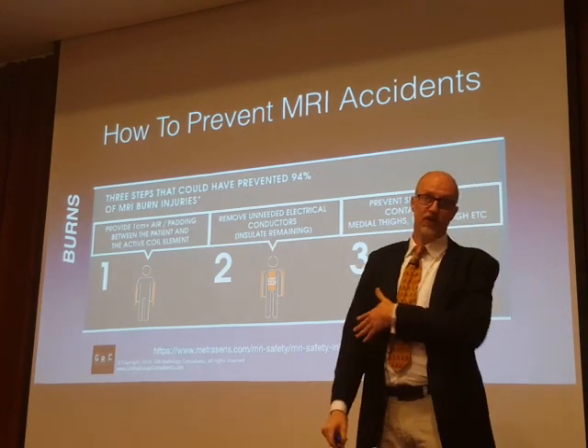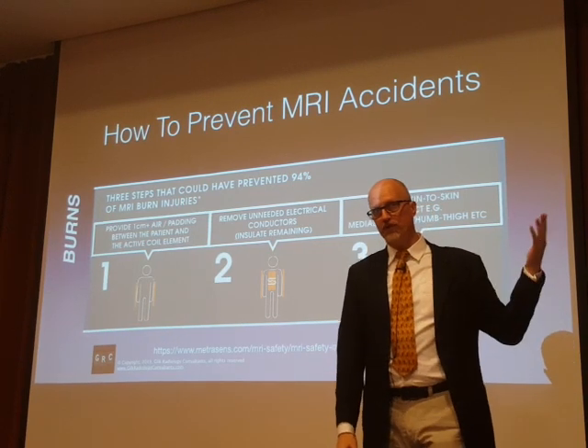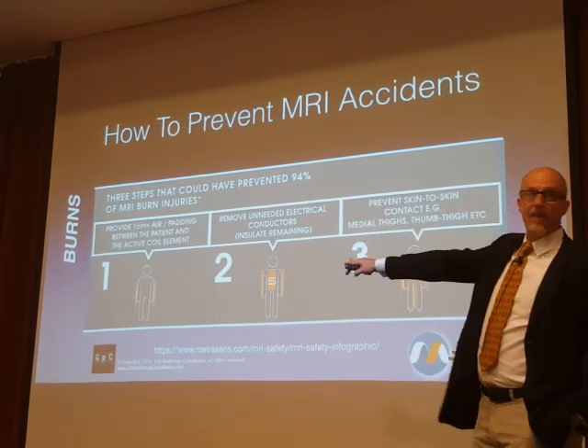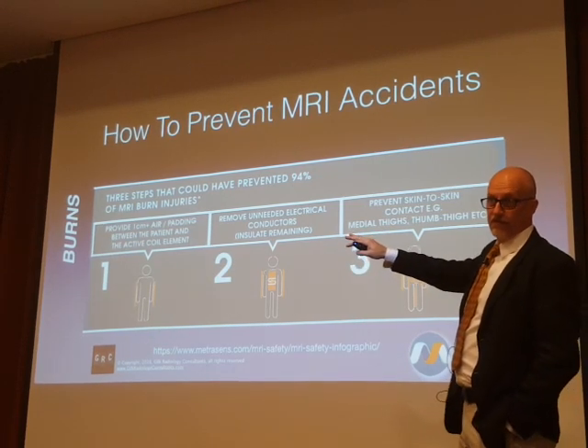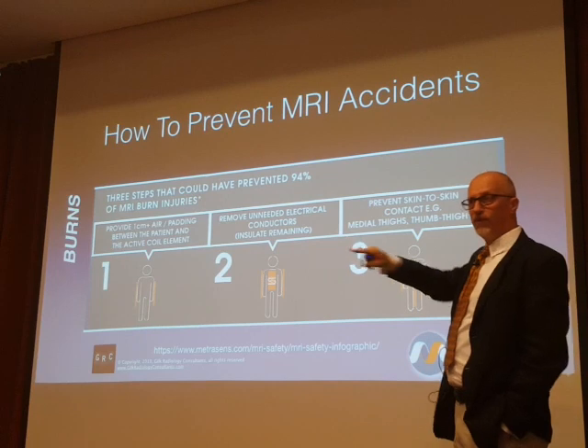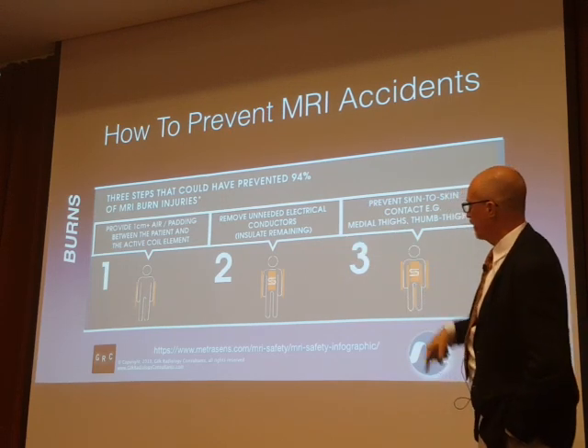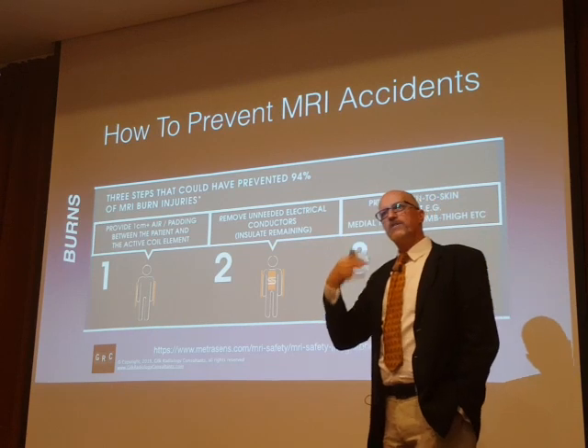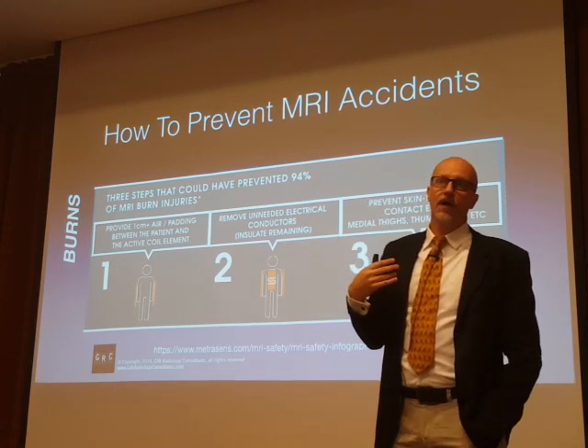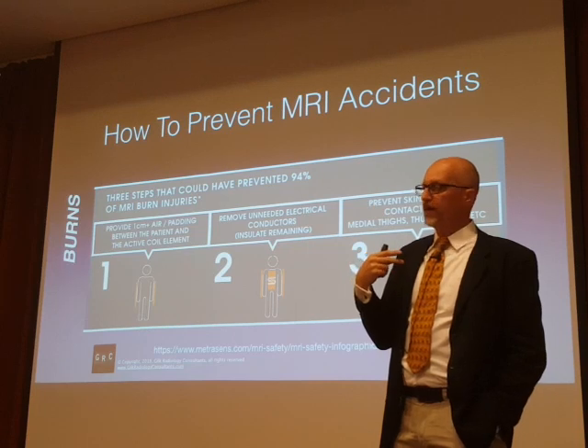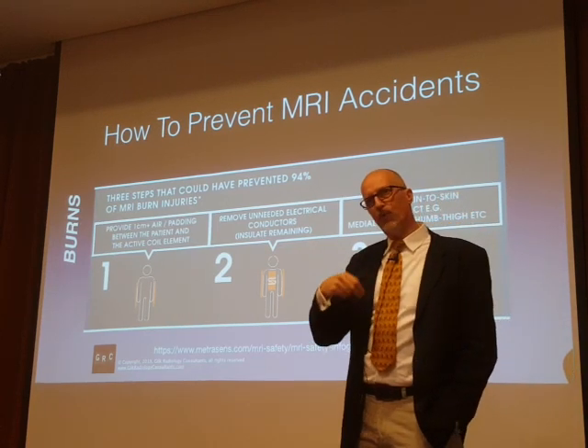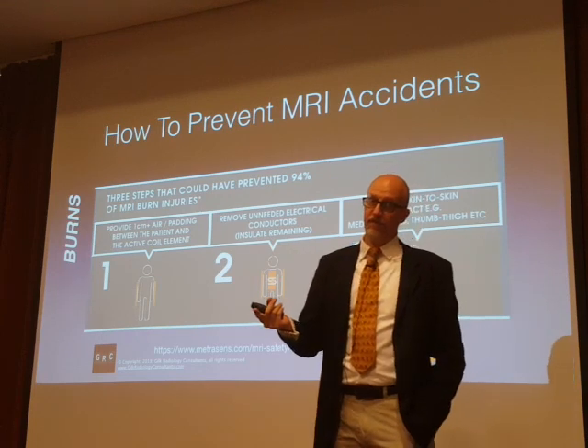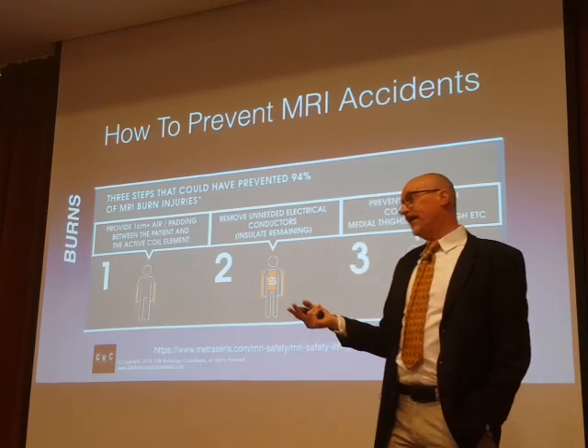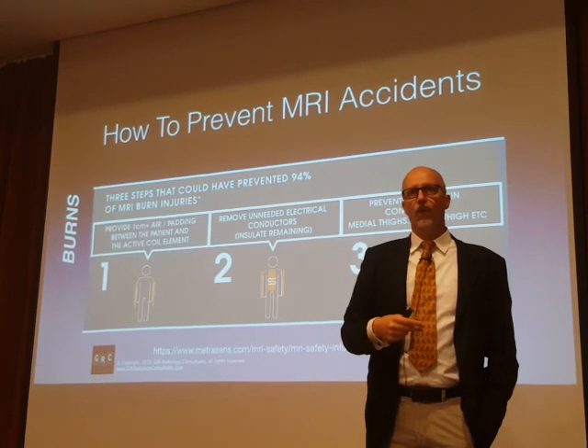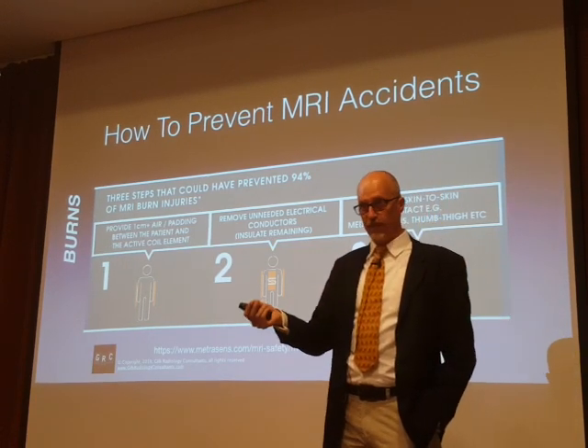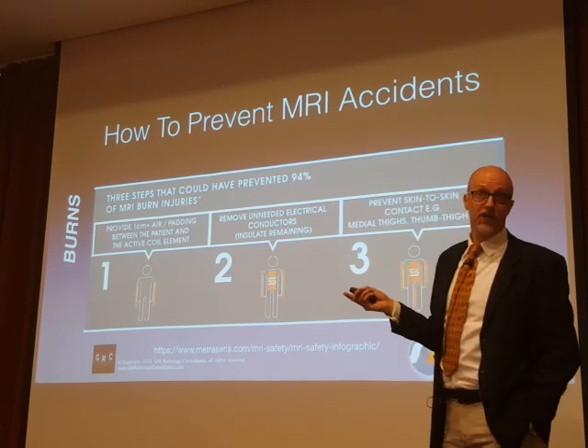There's what's called proximity burns, where the patient's tissues are too close to the transmitting element, and pads are almost 100% effective in terms of preventing that when you place them between the patient and the transmitting RF element. The second most frequent source of RF-related burns was an electrically conductive material in the bore with the patient. That might have been their clothing. It might have been an EKG lead or a pulse ox lead, or a coil cable for a coil element that was unplugged. It may have been the patient's own clothing.